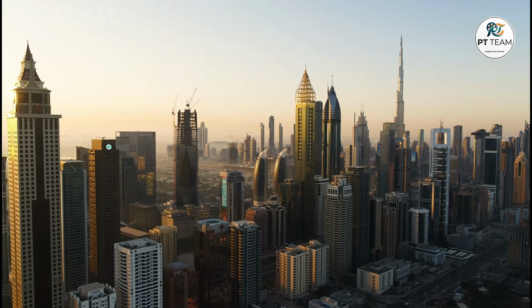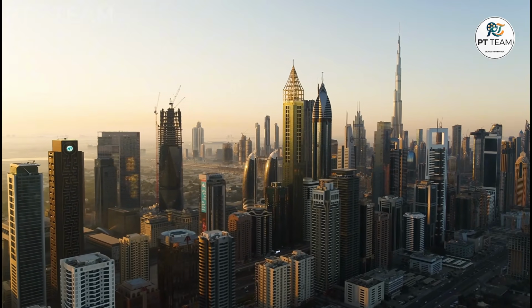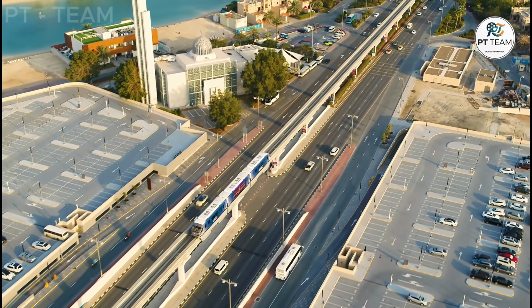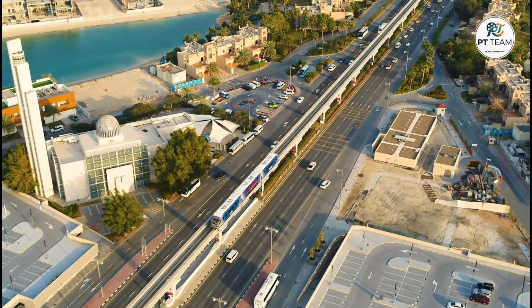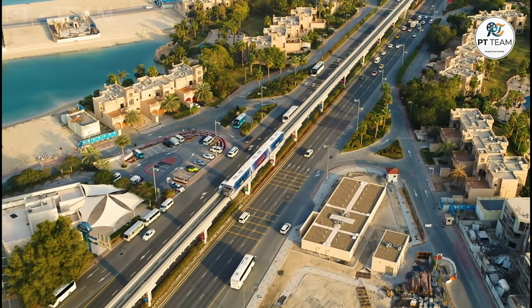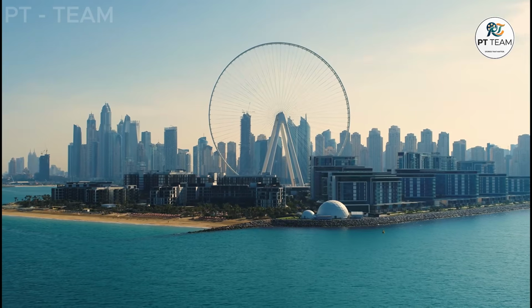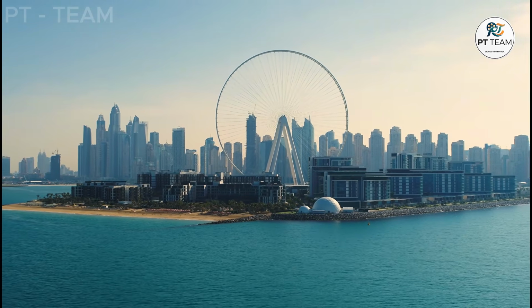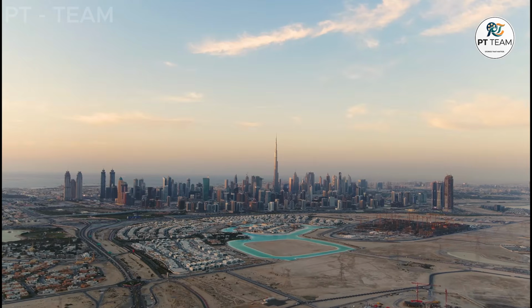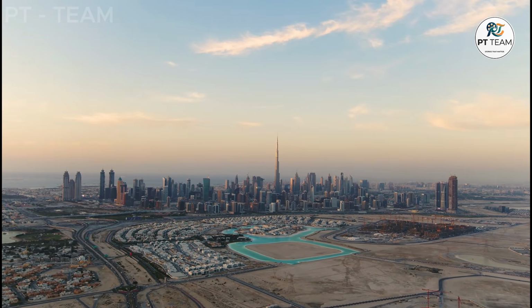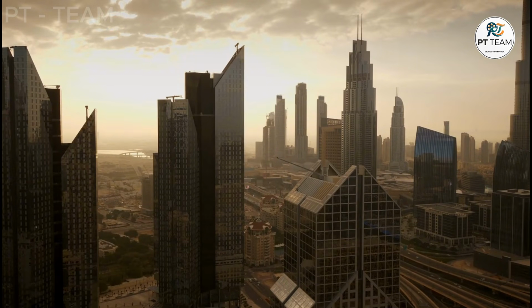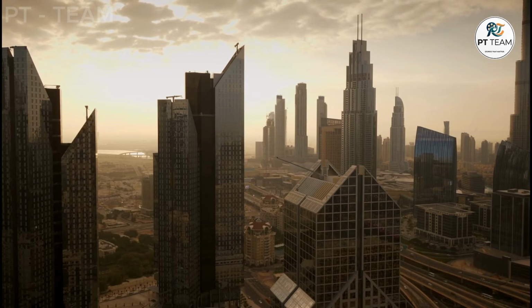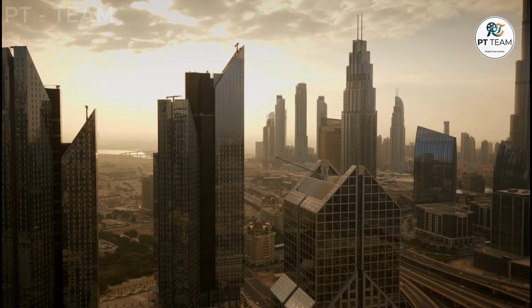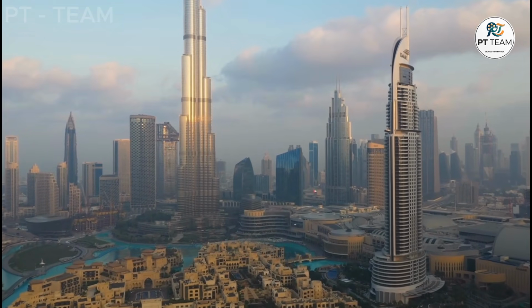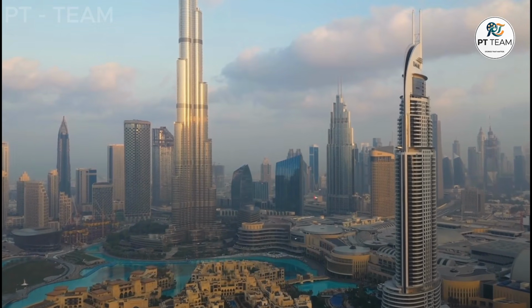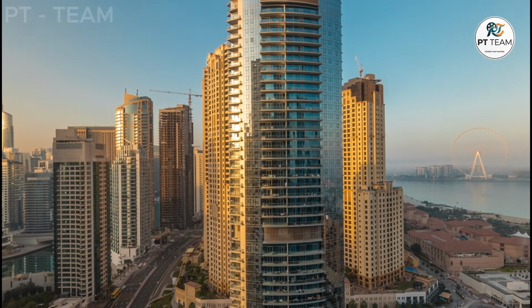If district cooling contains so many moving pieces and complex dependencies, why does Dubai keep building more of it? The undeniable answer is that centralized district cooling provides major, proven efficiency advantages compared to thousands of independent conventional air conditioners straining on separate balconies. A modern central plant can utilize massive industrial chillers, gigantic thermal energy storage tanks, and variable speed equipment that an individual residential apartment building simply cannot afford. Dedicated control rooms constantly monitor the underground network, and specialized maintenance teams ensure the heavy equipment runs at optimal thermodynamic efficiency. The network operator can expand the modular plant precisely as the surrounding district grows, achieving massive economies of scale that save enormous amounts of electrical energy over the long term.